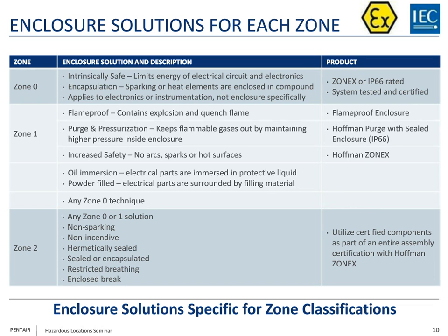You can purge and pressurize, which we've already talked about, or you can use a concept called increased safety. Increased safety looks like an IP66 type of enclosure, but the components being used within it don't arc, they don't spark, and they don't create hot surface temperatures on the enclosure themselves. Typically terminal boxes and control stations.